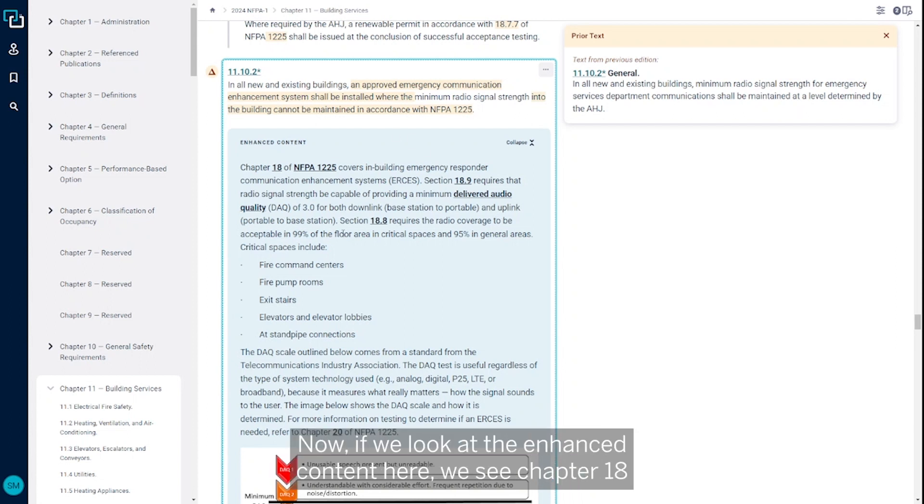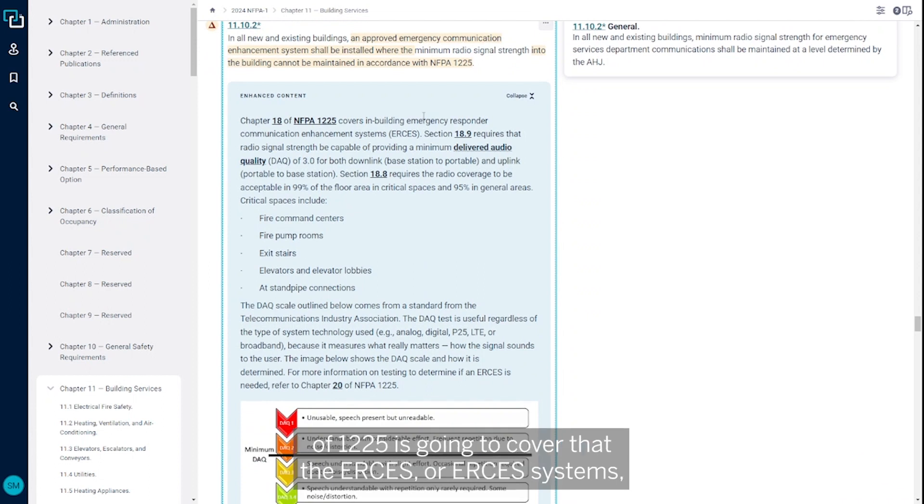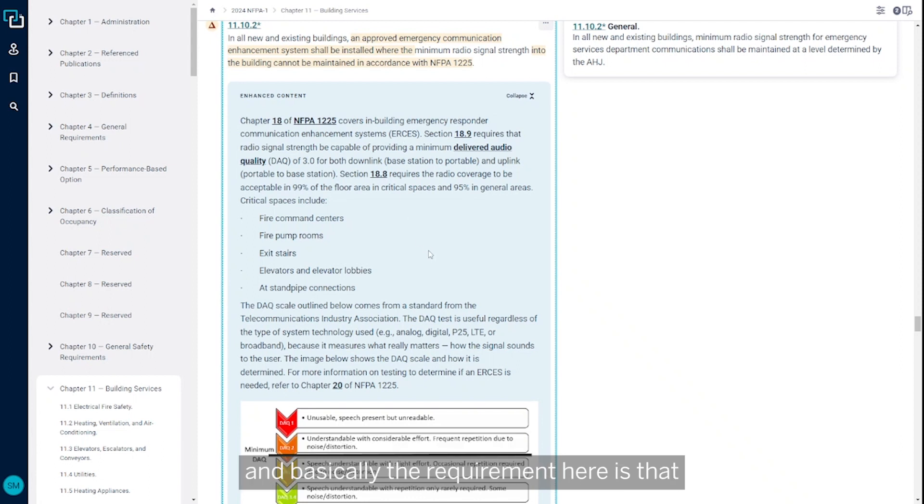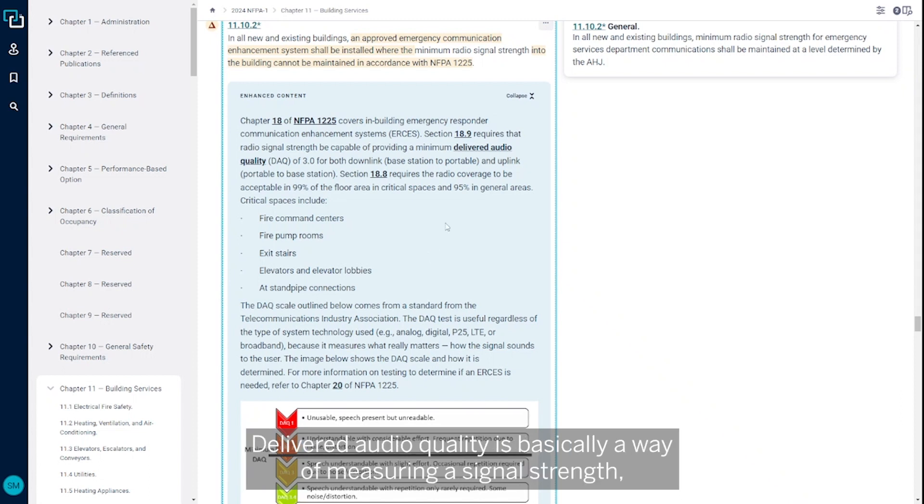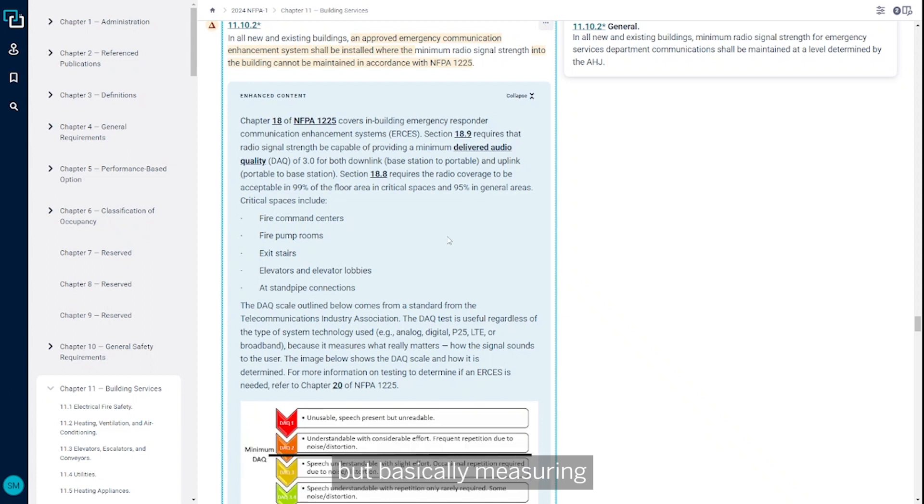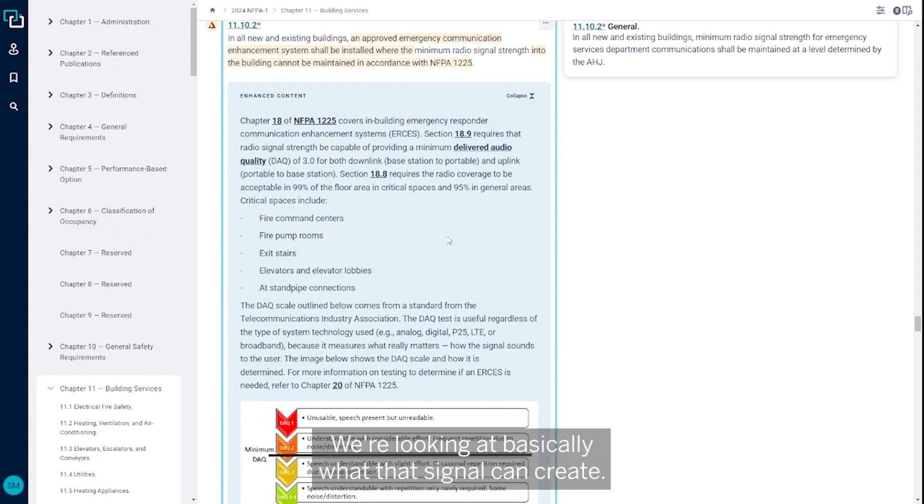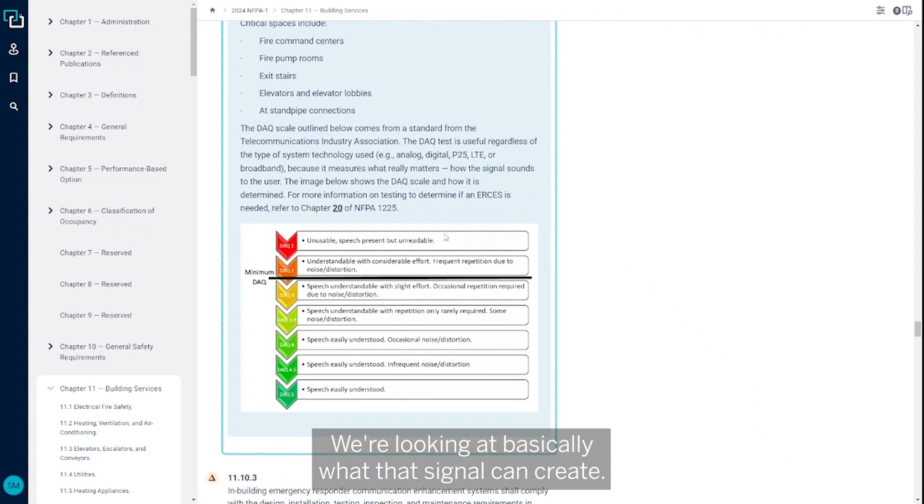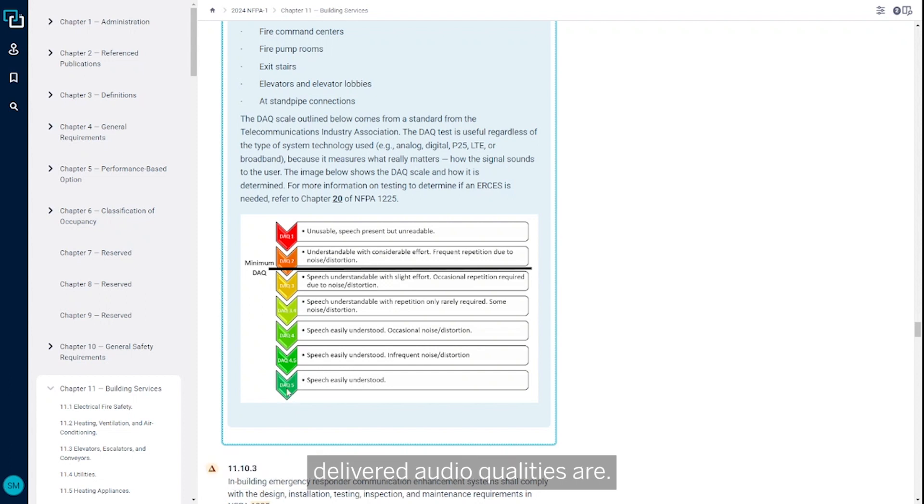If we look at the enhanced content here, Chapter 18 of 1225 covers the ERCES systems. The requirement is that we need to be able to provide a delivered audio quality. Delivered audio quality is a way of measuring signal strength, but instead of measuring how strong the signal is, we're looking at what that signal can create. Here's an example of what those different delivered audio qualities are.